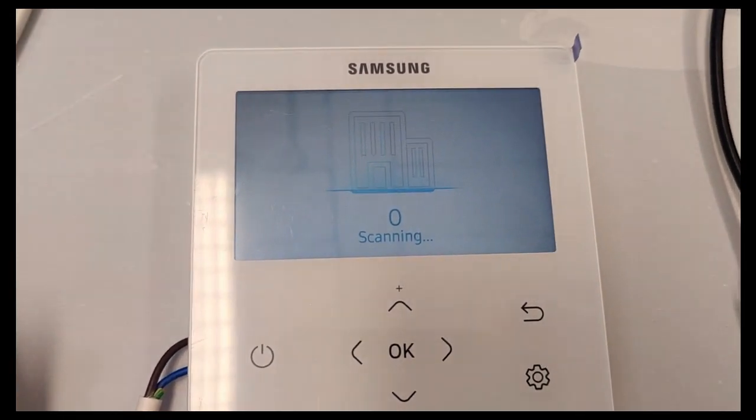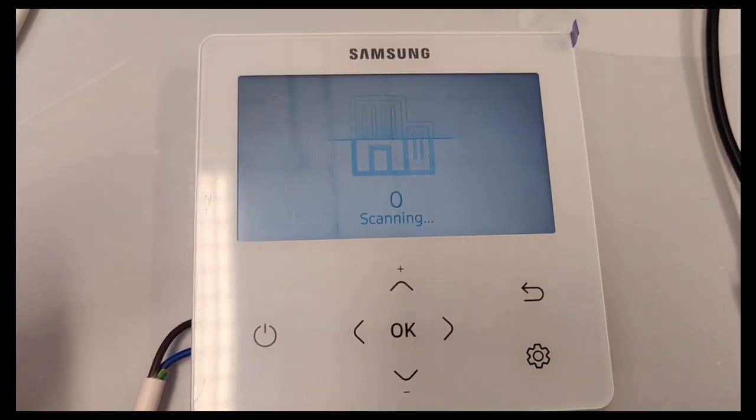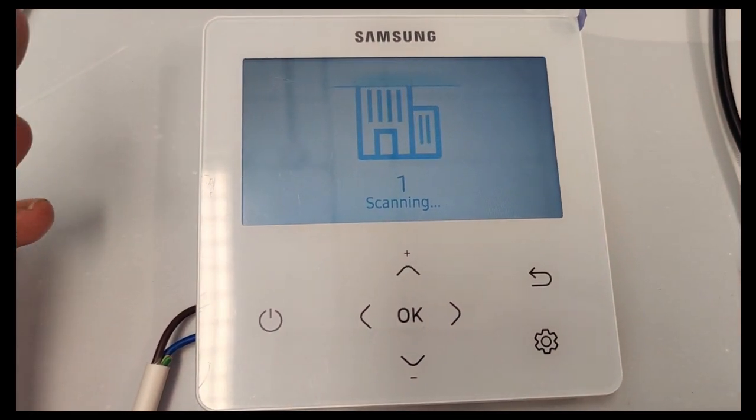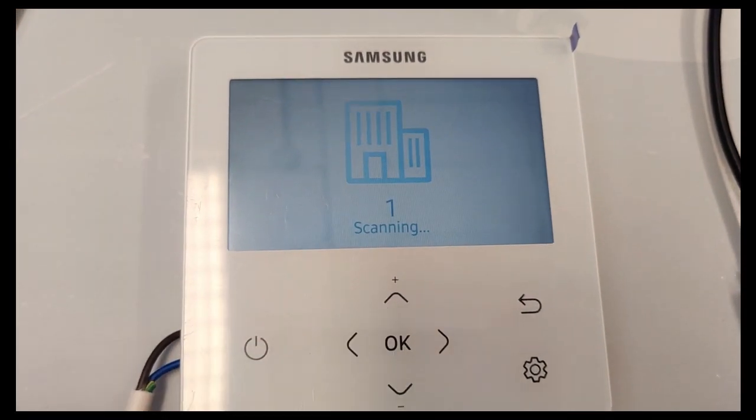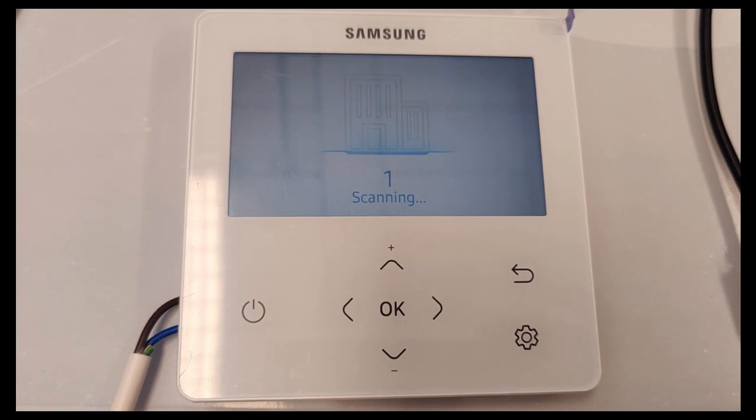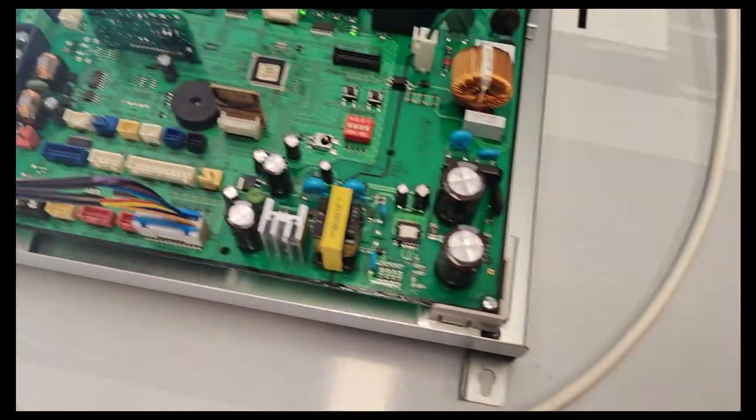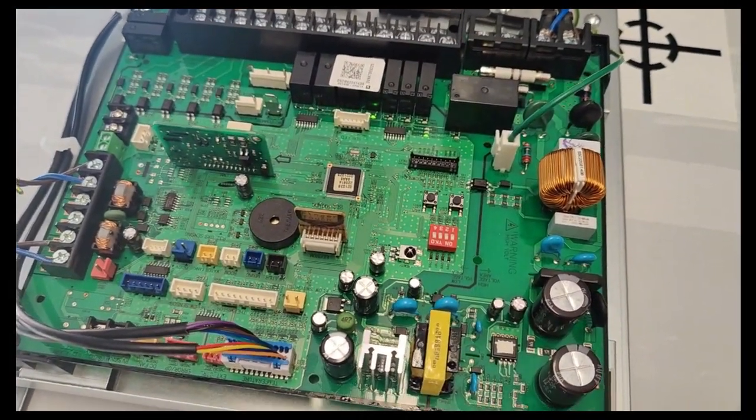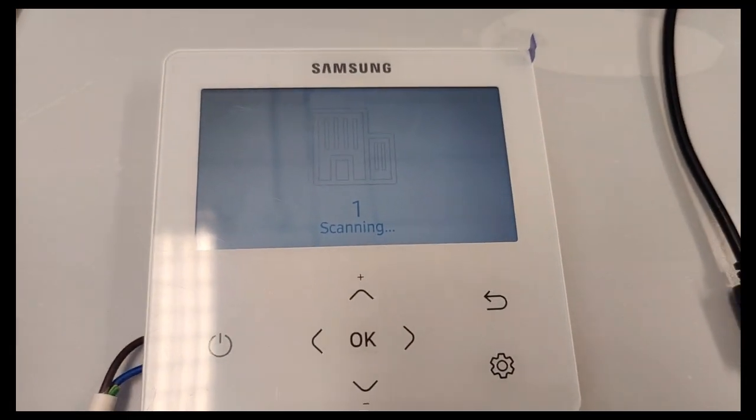And then it says scanning. Scanning zero means it's basically powering up and checking its indoor unit. Scanning one means that it can see between the indoor PCB, this one, the main one, and the outdoor PCB. So this is a good start.